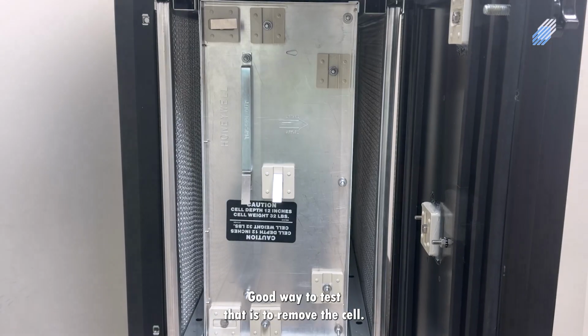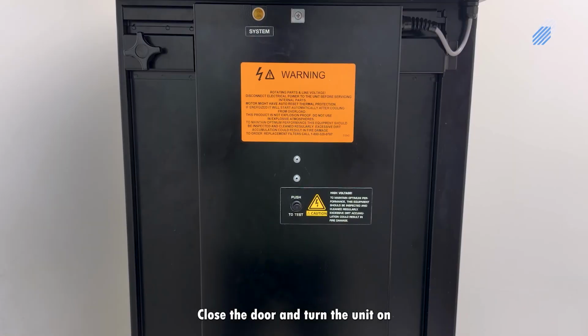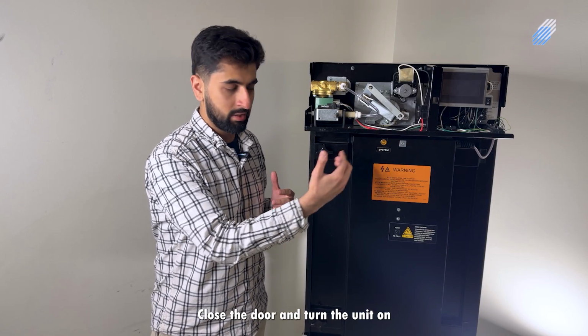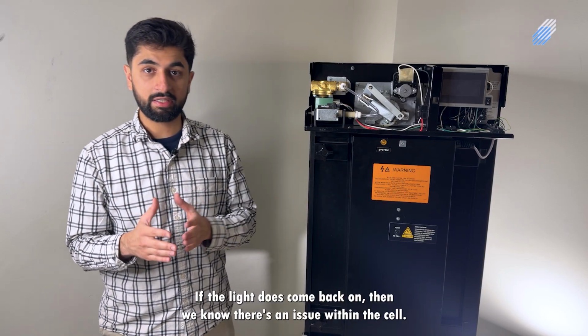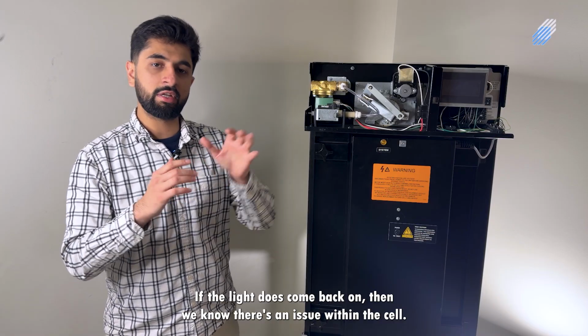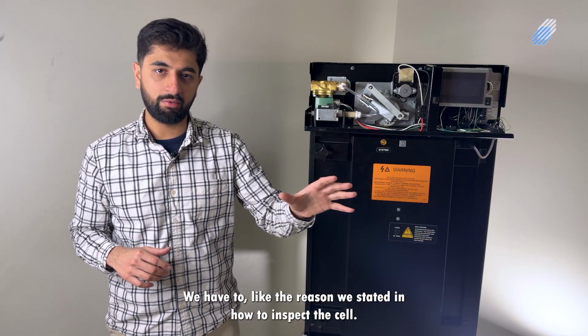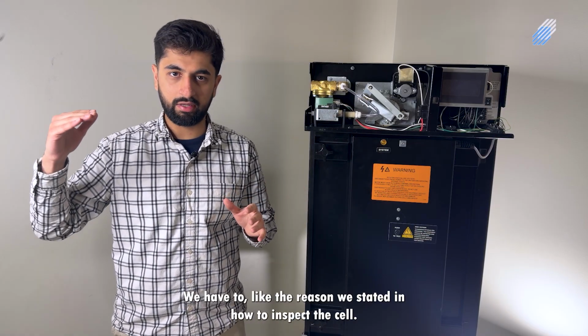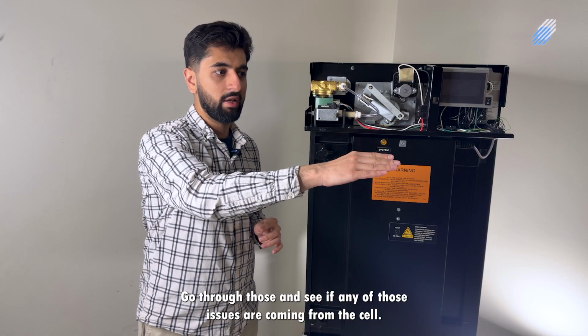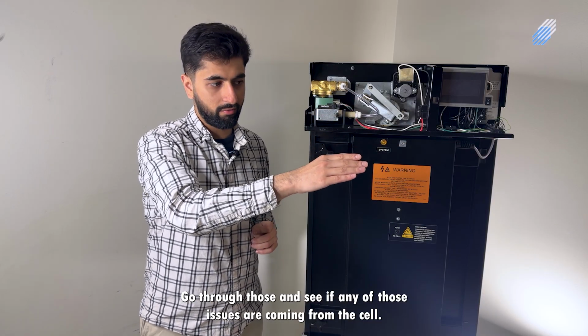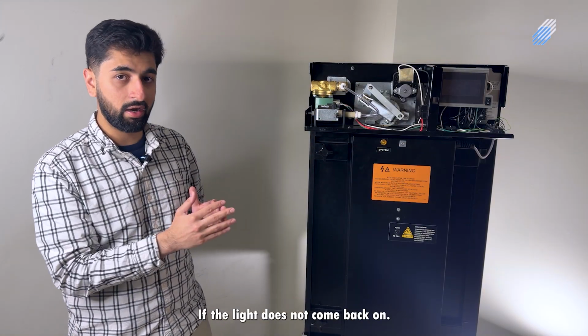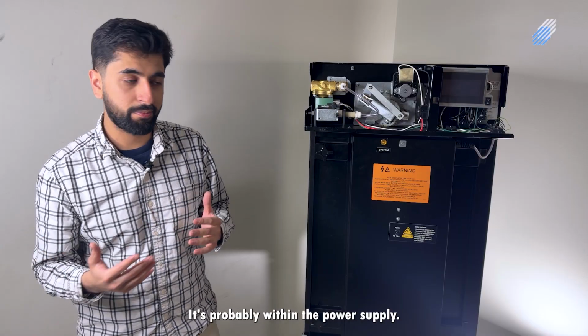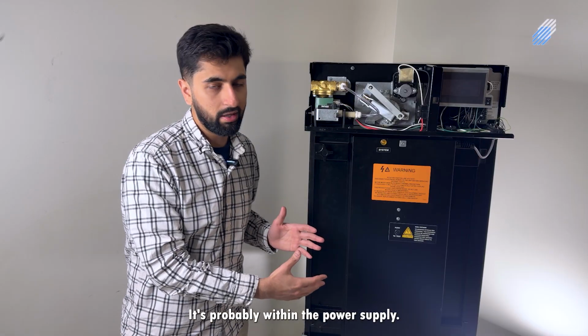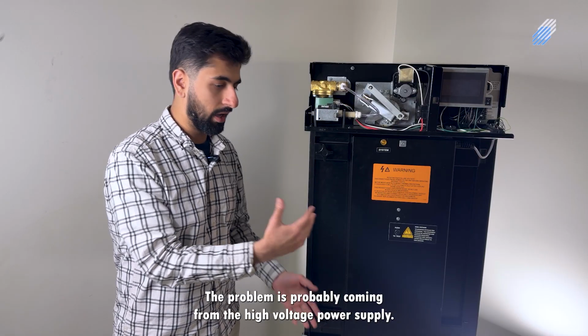A good way to test that is to remove the cell, close the door, and turn the unit on and see if the light comes back on. If the light does come back on, then we know there's an issue within the cell. We have to inspect the cell, going through the reasons we stated on how to inspect the cell, and see if any of those issues are coming from the cell. If the light does not come back on, then it's another issue. It's probably within the power supply. The problem is probably coming from the high voltage power supply.